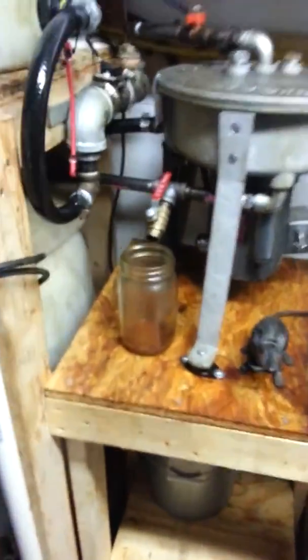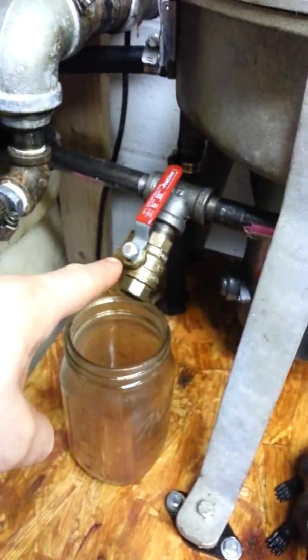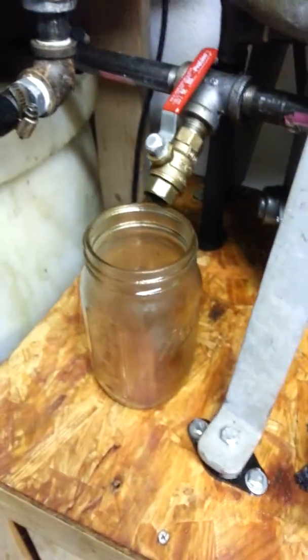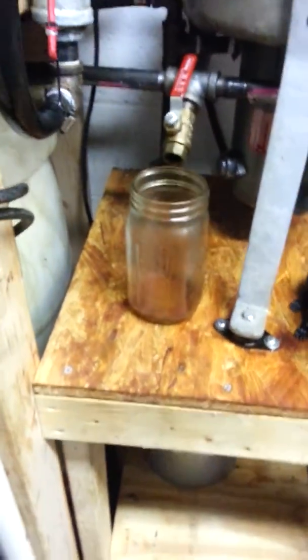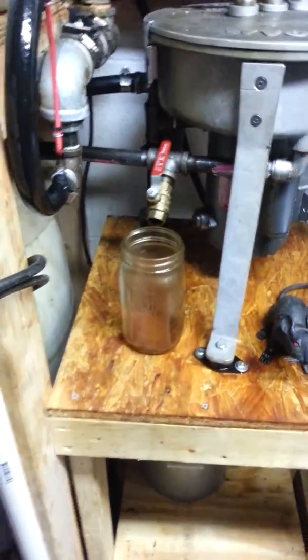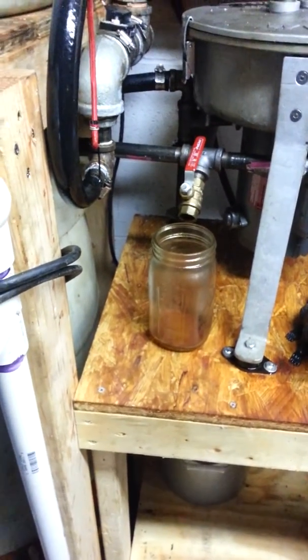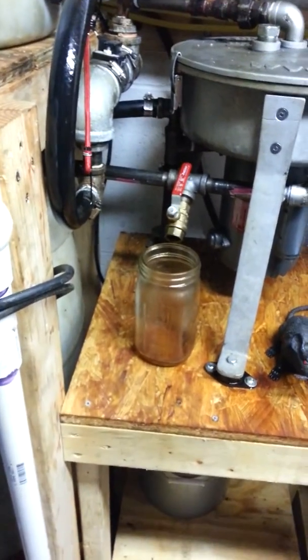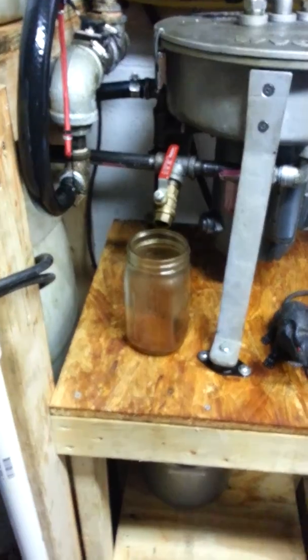This line right here is so I can test the flow of the oil. I just open this up, I have this bulge right here marked for every 4 ounces. 15 seconds to 4 ounces will get you about 8 gallons an hour. So once I get that real close, I'll check a total of 8 ounces for 30 seconds.